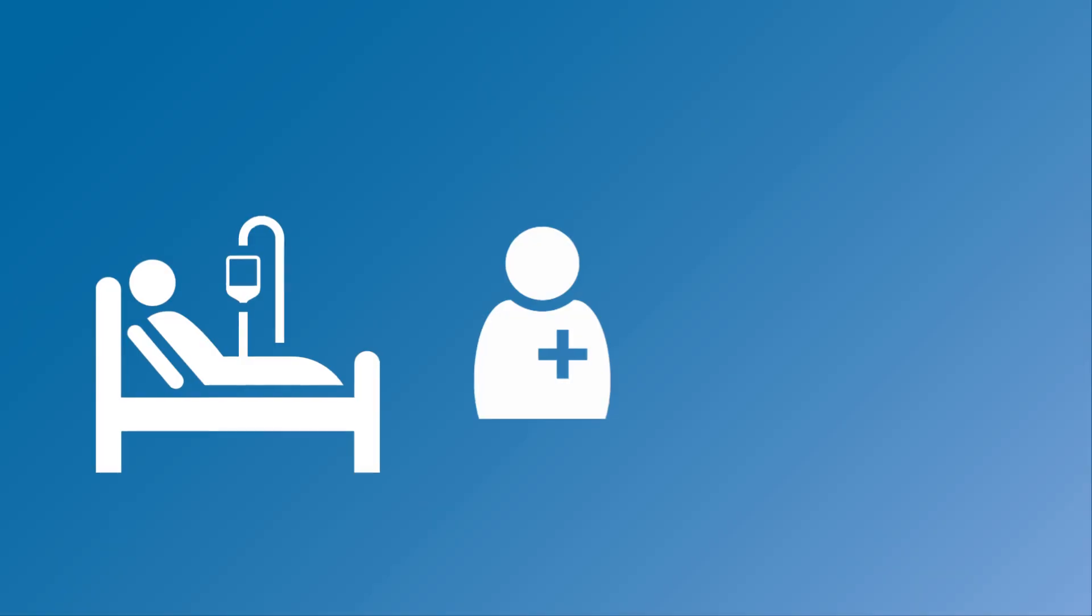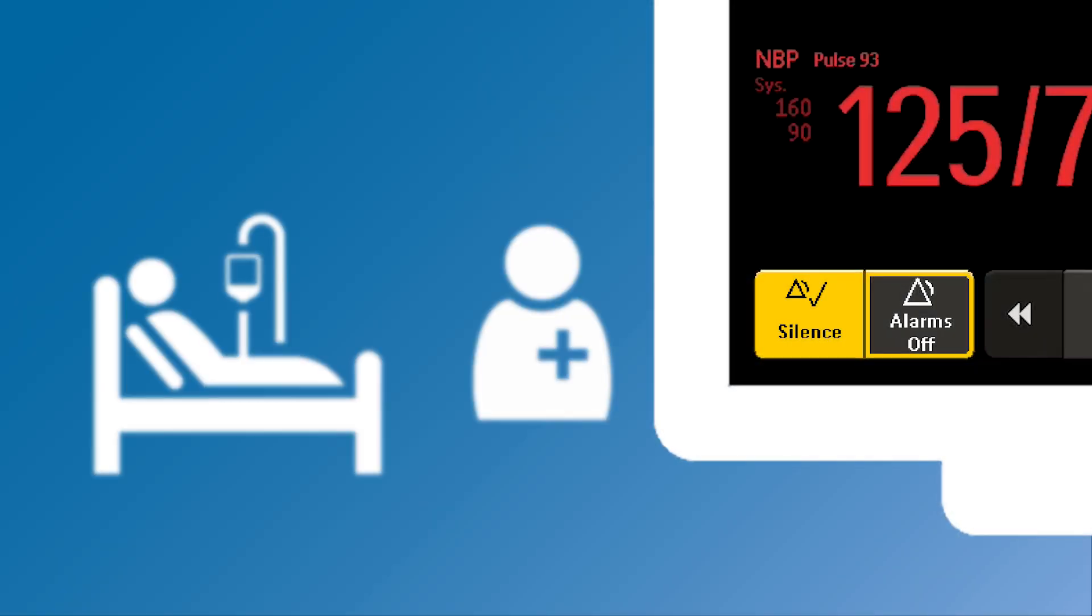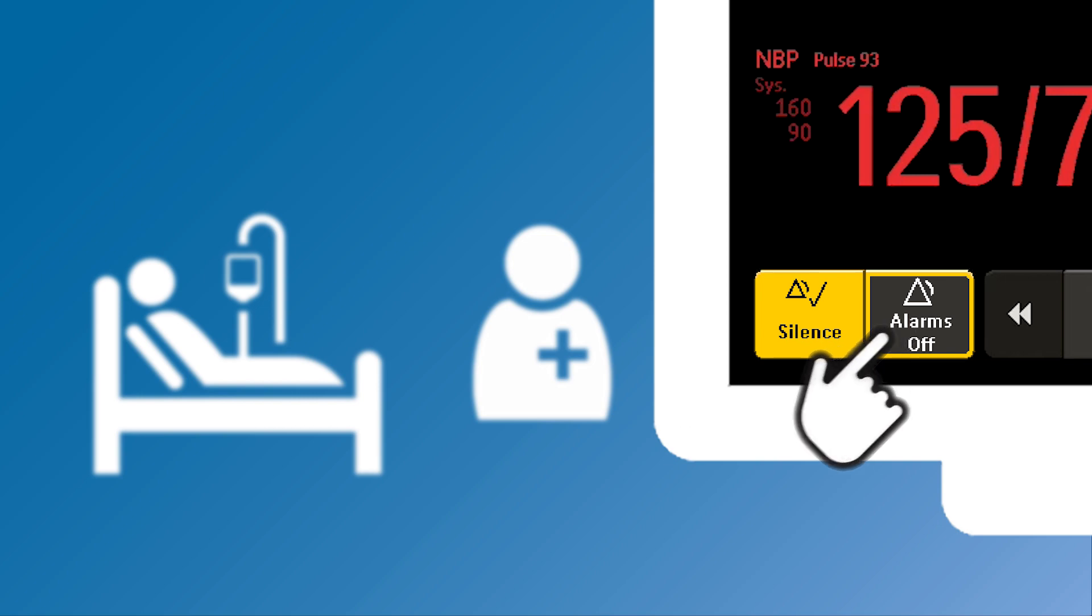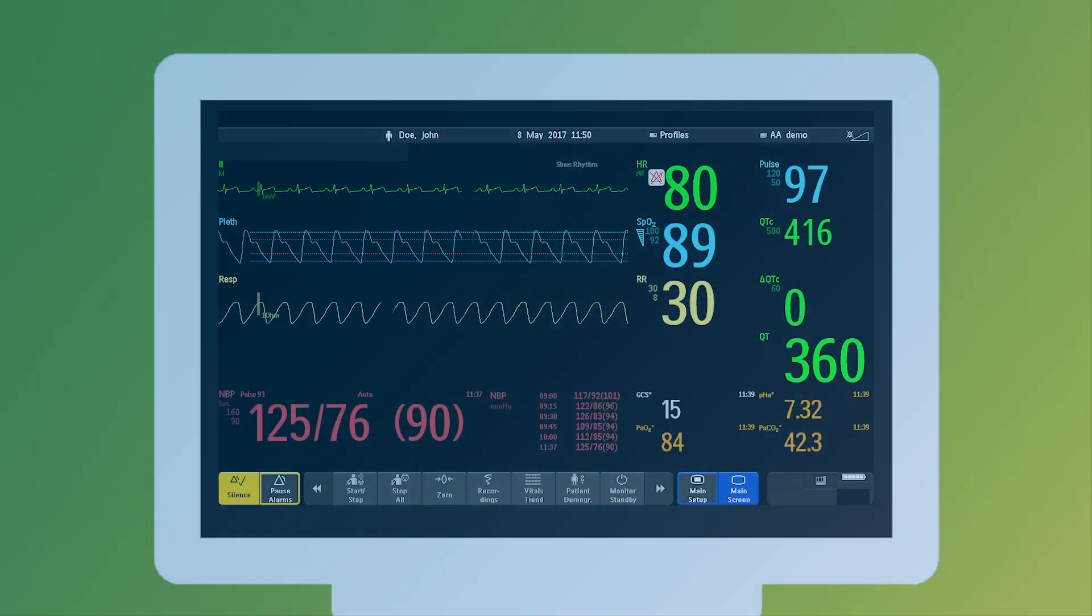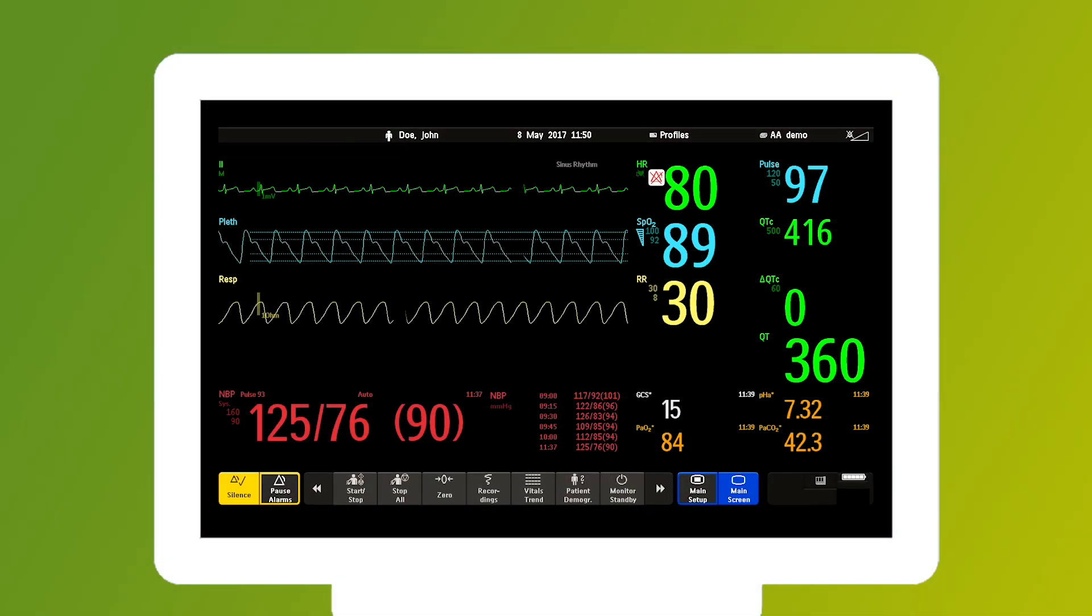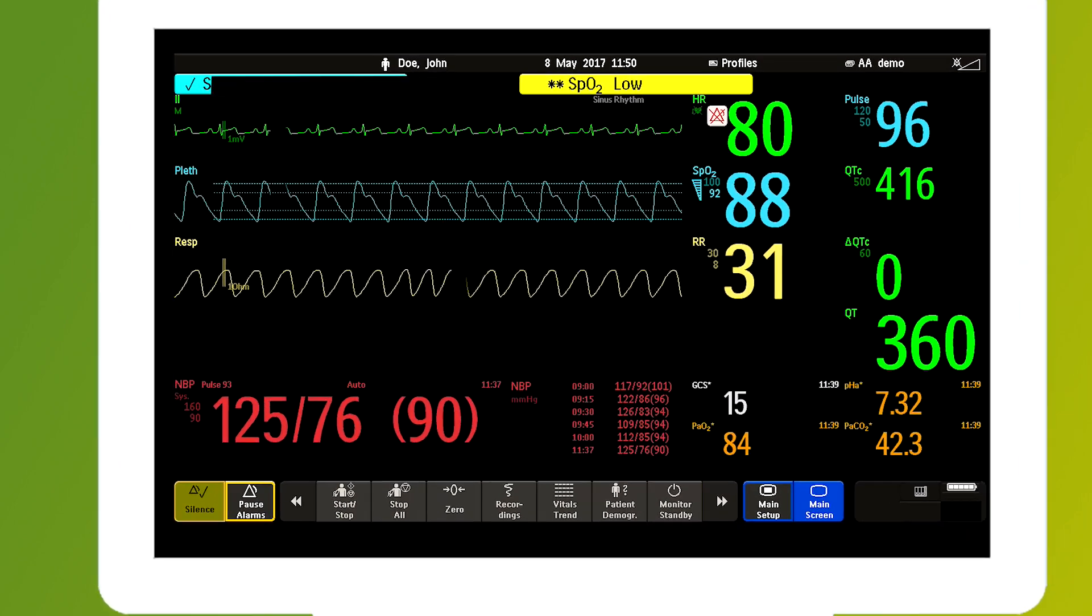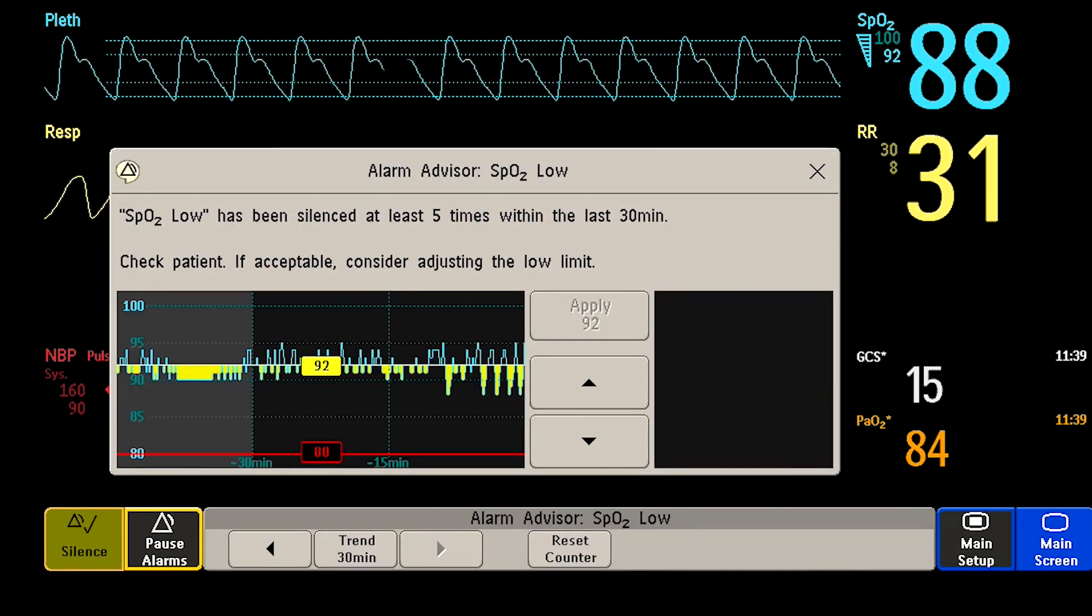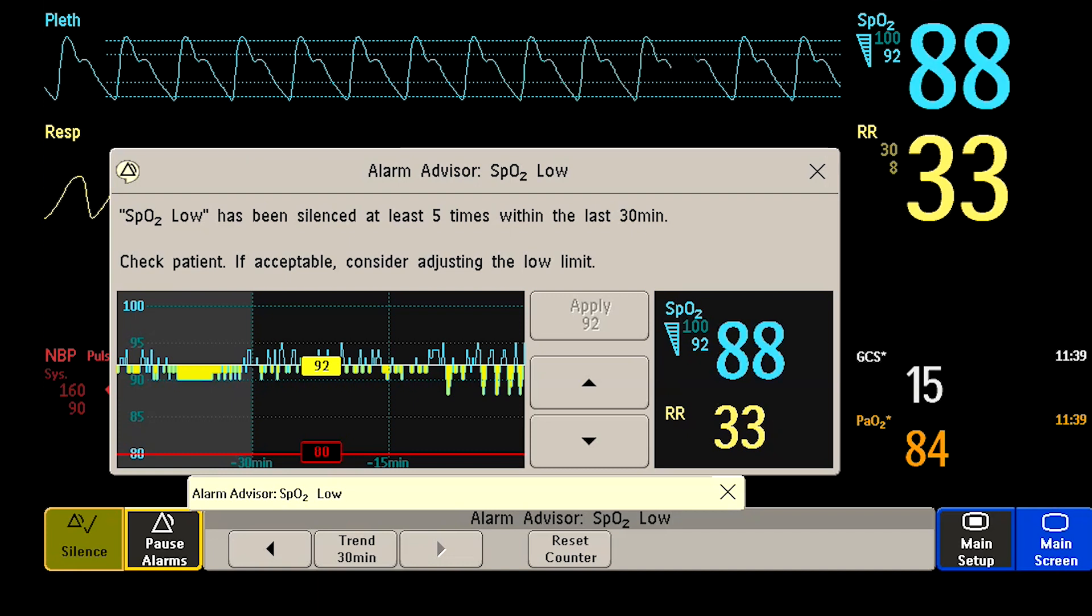Alarm Advisor is a clinical decision support tool that provides feedback on how you're responding to each patient's alarm. By tracking your silencing behavior, it can alert you when it appears that a patient's warning system may be too sensitive because their set thresholds are not appropriate for them.